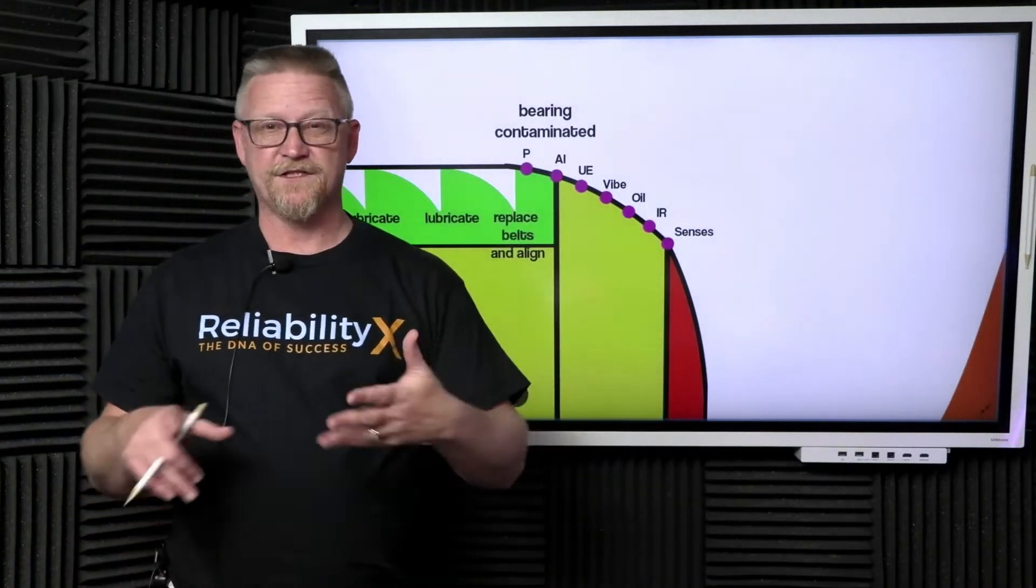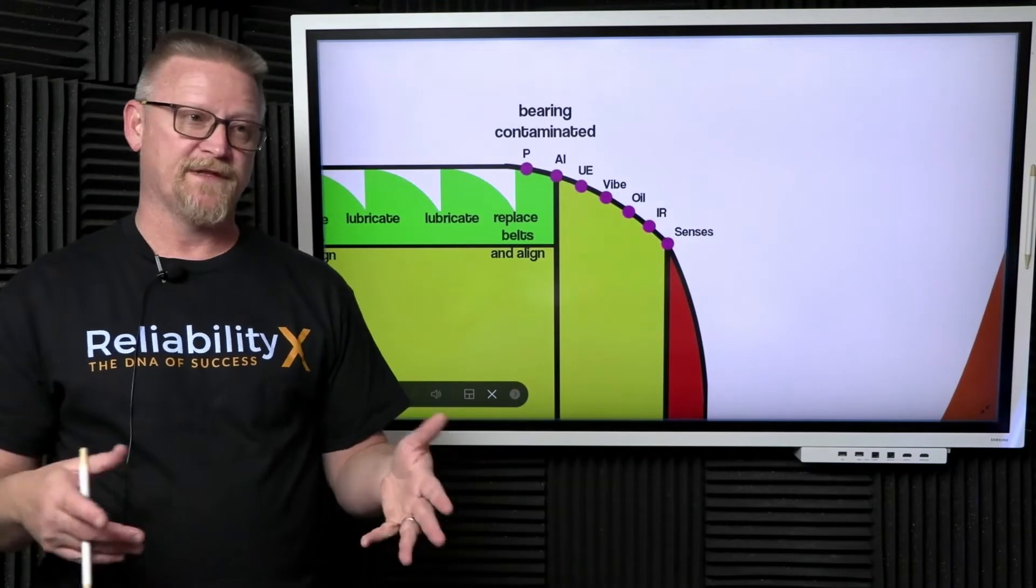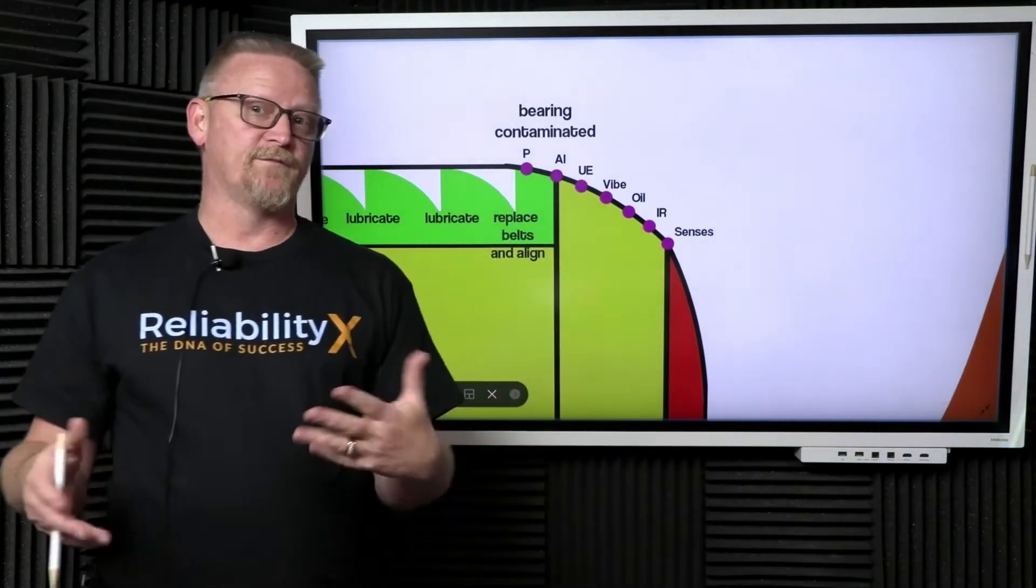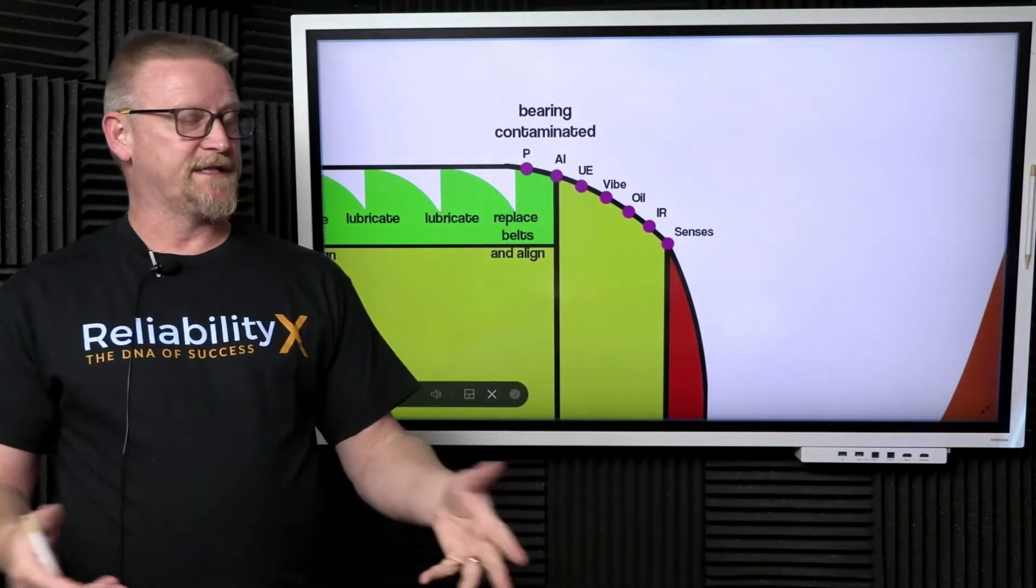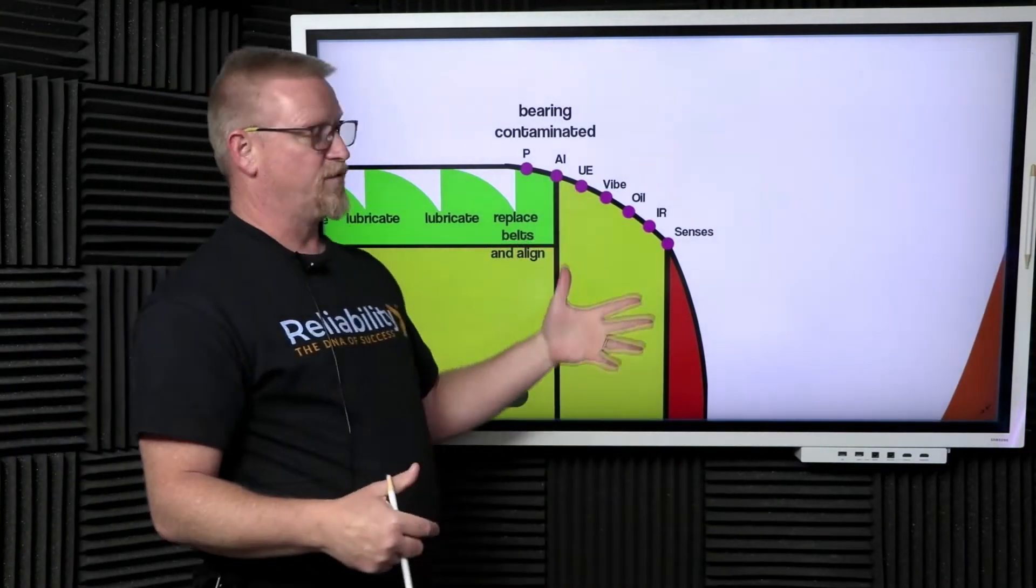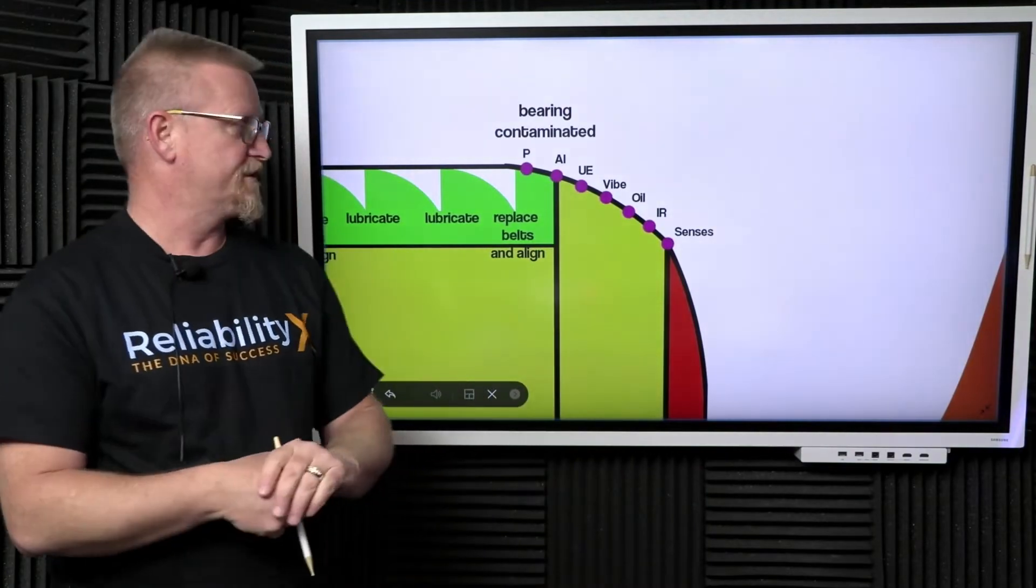There are things like artificial intelligence and machine learning—these can pick up things based on a variety of parameters. Then ultimately ultrasound can hear that there is contamination inside the bearing. Vibration analysis can pick up that there's something going on on a cage pass frequency or an outer race defect.